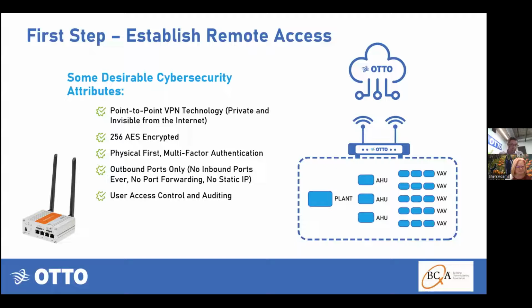Now, it's normal for us to have testing ongoing when all of a sudden the owner's IT comes around, makes their connections, and we have to update some network settings on our device to work with their system. If they won't allow them to be connected at the same time, sure, we can temporarily keep the networks disconnected, meaning essentially just physically disconnect the owner's network for the purposes of testing and reconnect when we're done. So there's lots of different ways to approach this, but having the flexibility of cellular or on-site internet makes it a lot easier process.